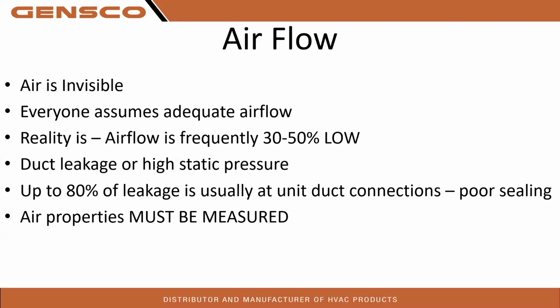Duct leakage or high static pressure. I think back to some of my early installations 20 years ago. We were using that gray duct tape with no panduits and nothing else. And I was using a chainsaw to cut holes and stuff. And I think back, man, there's going to be some air leakage. And I've actually ripped out some of my systems that I did years back and sealed everything pretty well. Up to 80% of the leakage is usually at the unit duct connections, right? Like we were saying, poor sealing, hard pipe and mastic sealing is always the best.